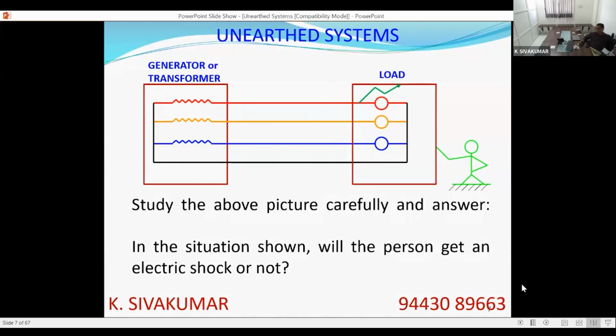Generally speaking, there will not be any closed circuit here, because the person is standing on earth, but the neutral is not connected to earth. So there is no closed circuit. For a basic understanding, there will not be current flow through the human body, even in this condition. Leave alone the high-end complicated subject of capacitive coupling. We will come to that later. But to start with, since there is no closed circuit, there will not be any current flow, even in the case of a single phase to ground fault. We will come to the intricacies later.